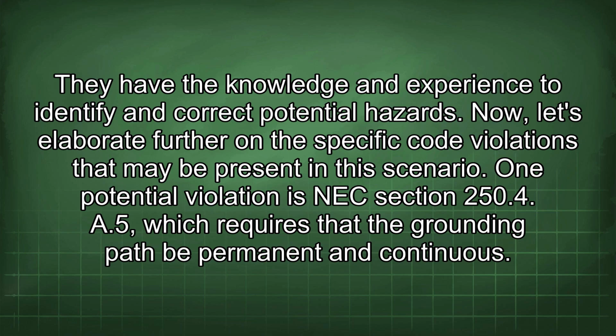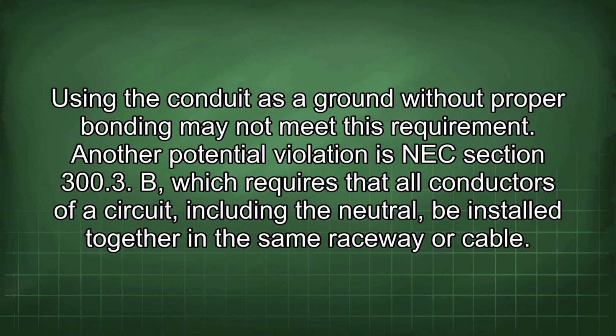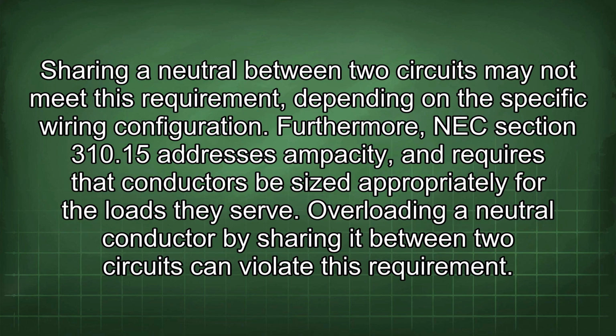One potential violation is NEC section 250.4(A)(5), which requires that the grounding path be permanent and continuous. Using the conduit as a ground without proper bonding may not meet this requirement. Another potential violation is NEC section 300.3(B), which requires that all conductors of a circuit, including the neutral, be installed together in the same raceway or cable. Sharing a neutral between two circuits may not meet this requirement, depending on the specific wiring configuration.